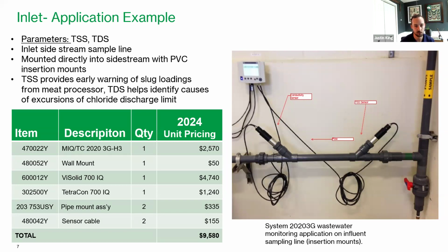And so the TSS sensor in this application is used to provide an early warning of any slug loading. So in this particular case, upstream, we had a meat processor plant, and a lot of meat processing waste was received at this plant. And that excessive waste caused problems later on in the plant. So they were able to monitor the inlet of the plant to ensure that they weren't receiving excessive loads that could affect the plant's processes later on.